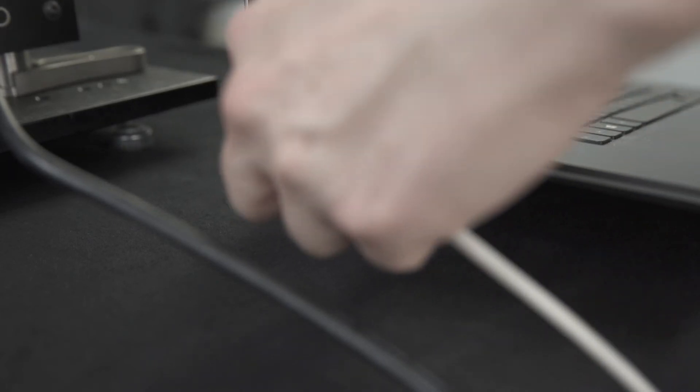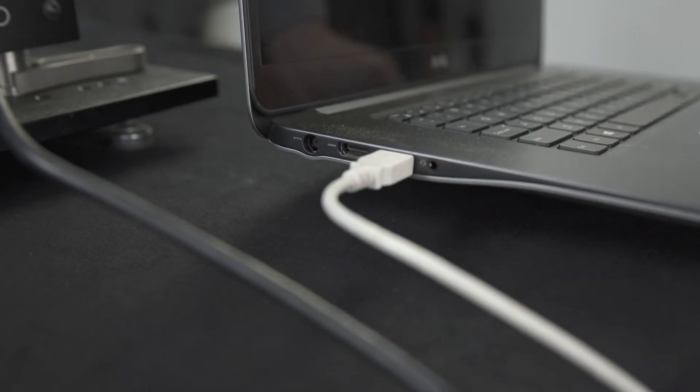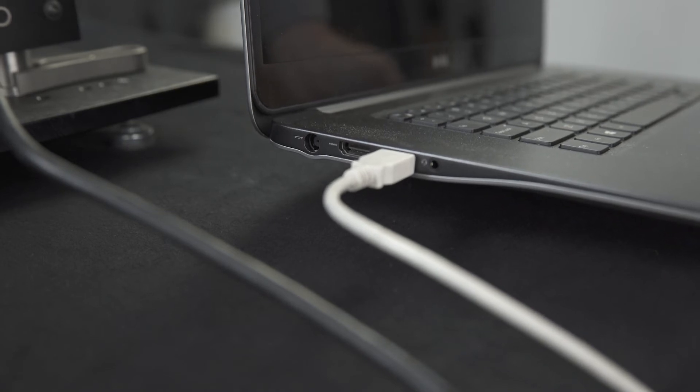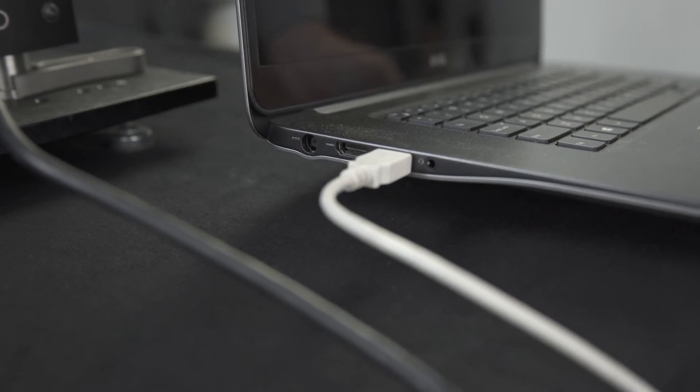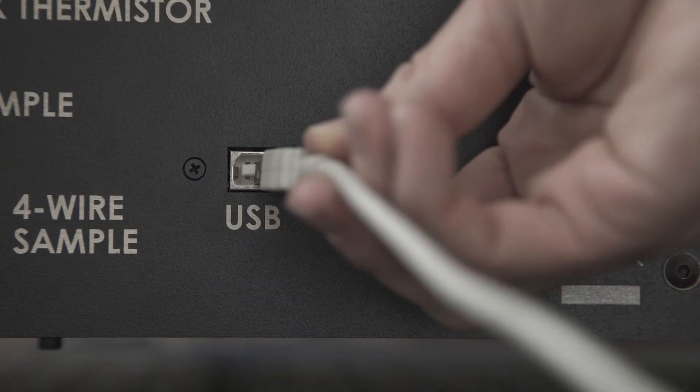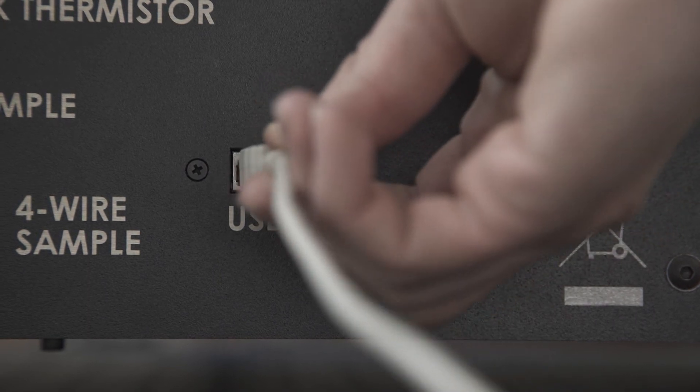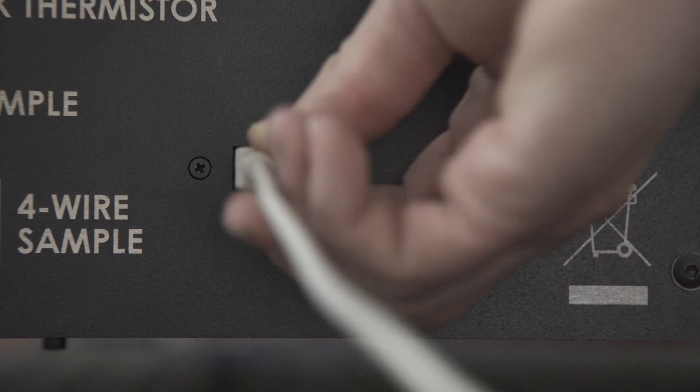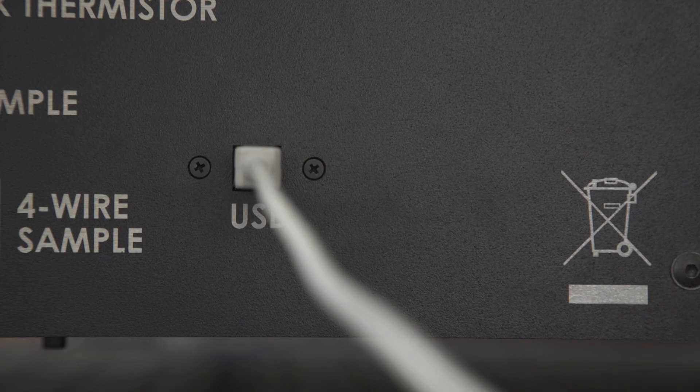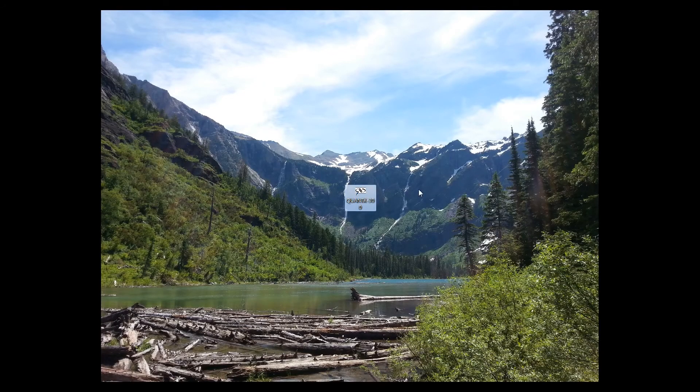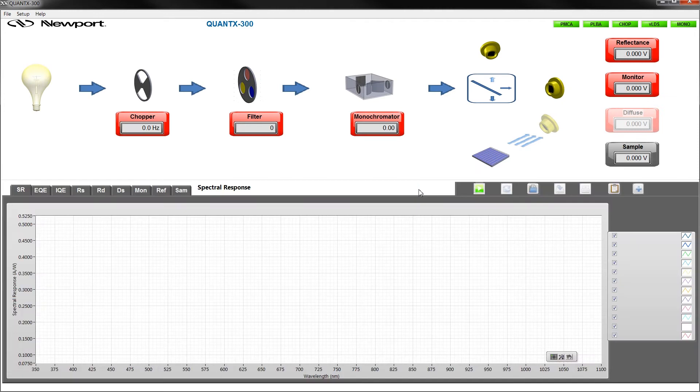Next, power on the laptop supplied with the equipment. After startup, connect the USB cable to a port on the laptop and the other end into the port on the rear panel of the instrument. This port is denoted by the USB symbol. Now we can initialize the software program by opening the shortcut from the desktop. Check that all components in the top right corner have been initialized correctly, denoted by the icons turning green.